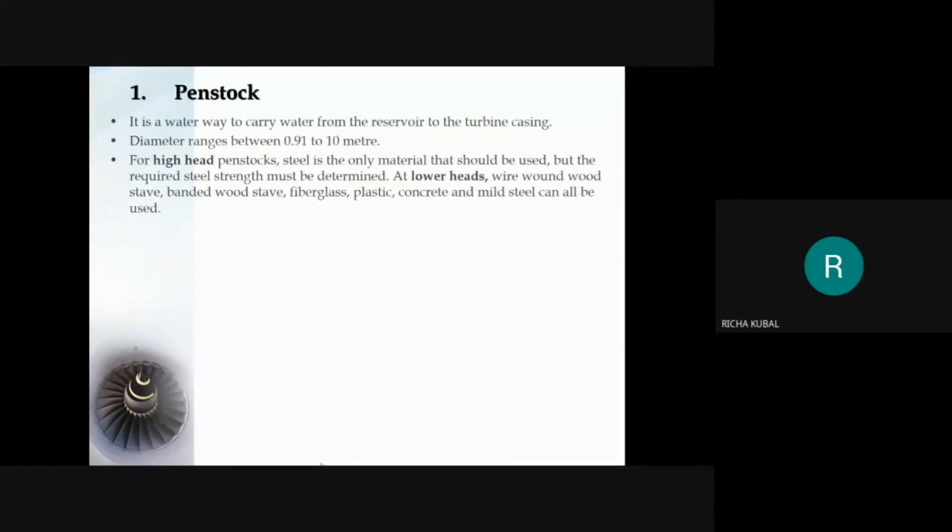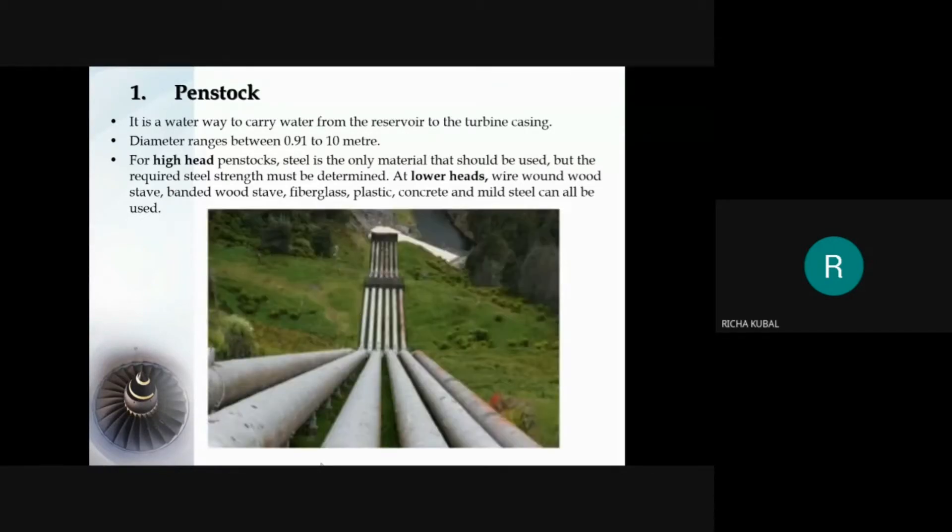First, penstock. The penstock is a pipe carrying water from head gate to water wheel. The penstock used in Francis turbine has a diameter ranging from 0.91 to 10 meters. It is an enclosed pipe that delivers water to turbine system and also controls the water flow. The material used to manufacture penstock is steel usually for high head penstock while for low head plastic, concrete, or mild steel is also used.